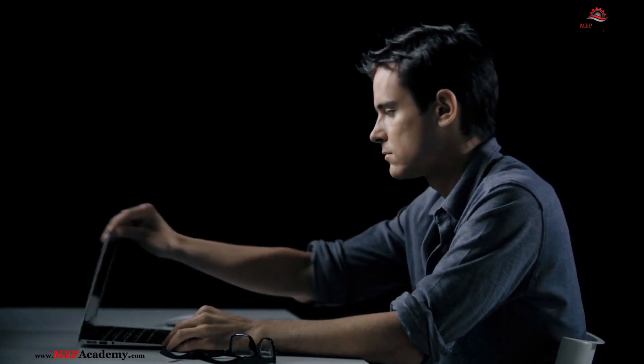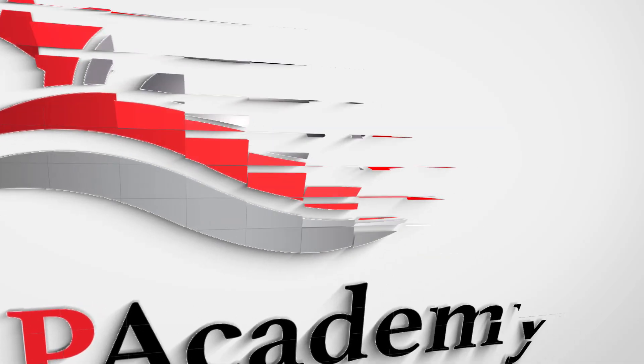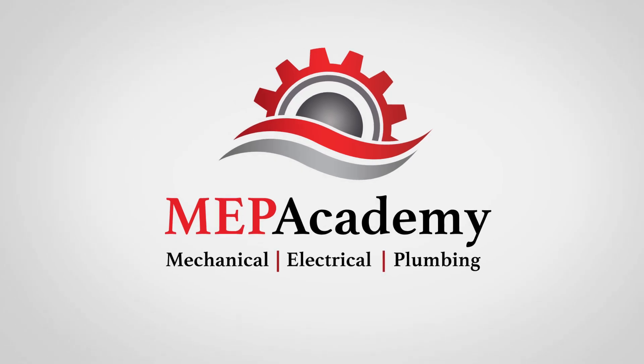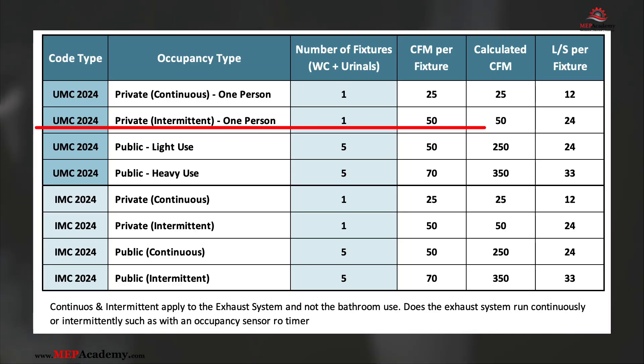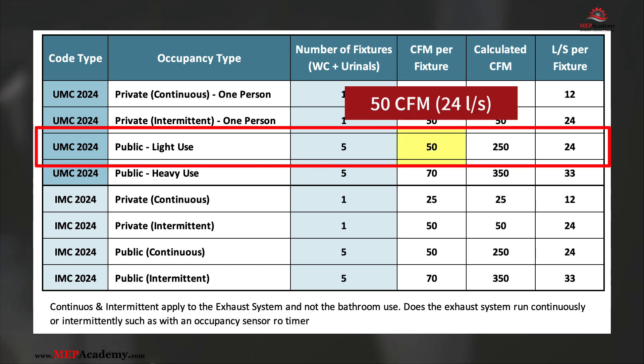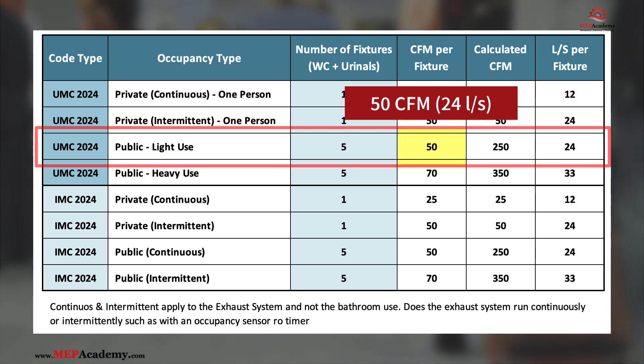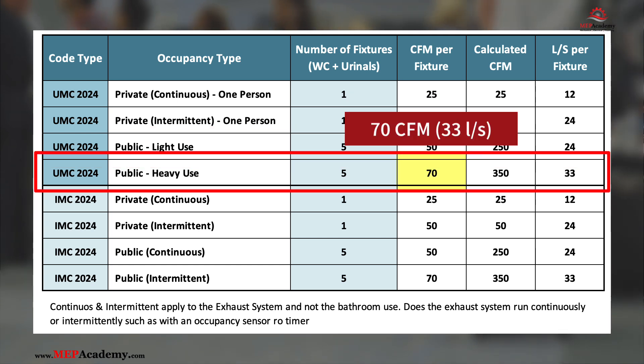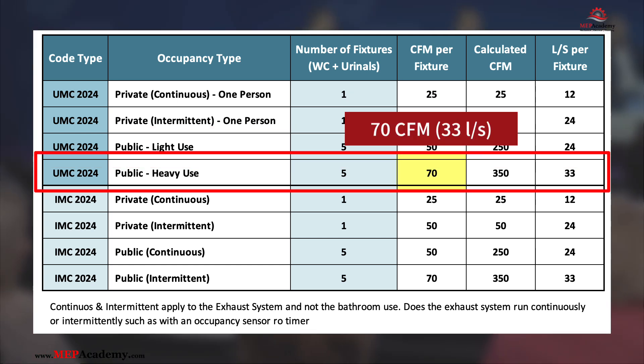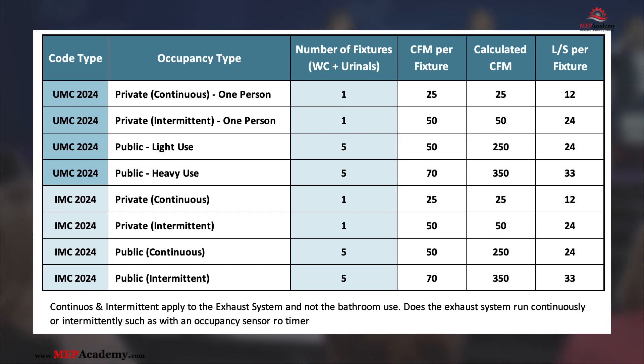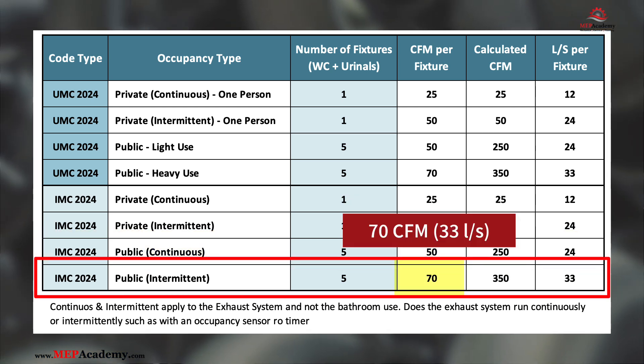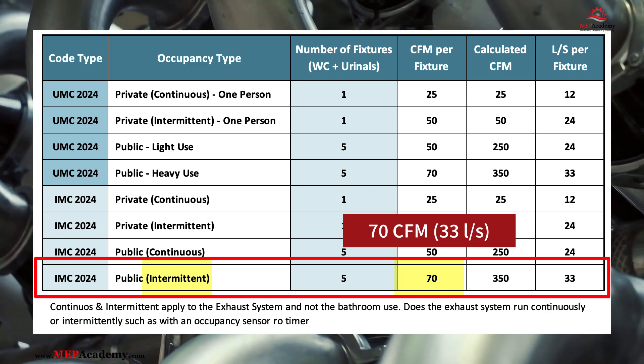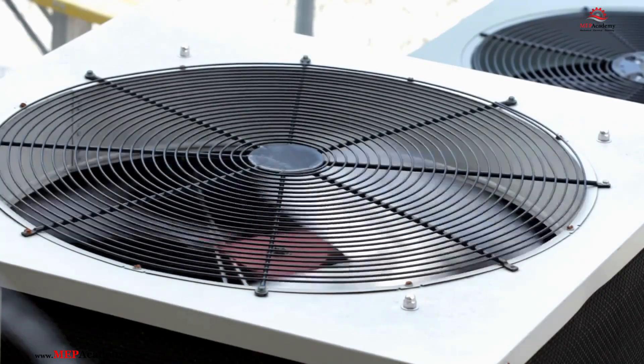Let's start with the basics. According to the 2024 UMC, light-use public toilet rooms require 50 CFM per water closet or urinal. Heavy-use areas like stadiums or airports may require 70 CFM per water closet or urinal. The 2024 IMC is similar: 50 CFM per water closet or urinal if the fan operates continuously, or 70 CFM per fixture if the exhaust system runs intermittently.